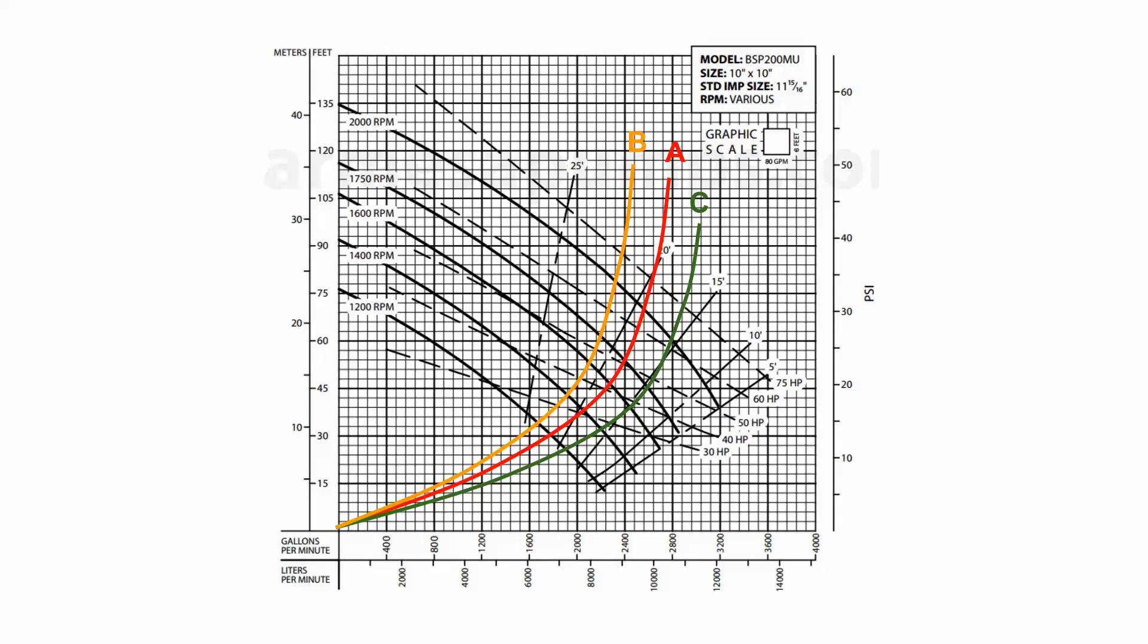Now let's say that you had a goal of having this pump in your facility. Let's say your goal is achieving the most flow, however you're limited and must do this with less than 50 horsepower. Well, you've run the numbers and you've come up with three possible system curves or three possible system layouts using various fittings and pipe material. What you've come up with in these three layouts is that by using system curve C, you can achieve a little bit more flow than the other system curves, and that's because you're minimizing your friction loss in that particular configuration.